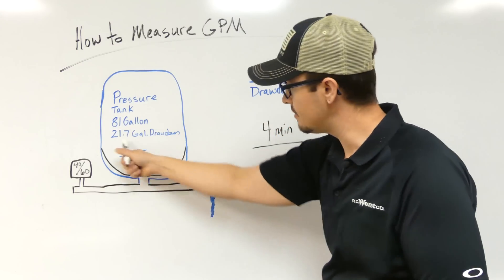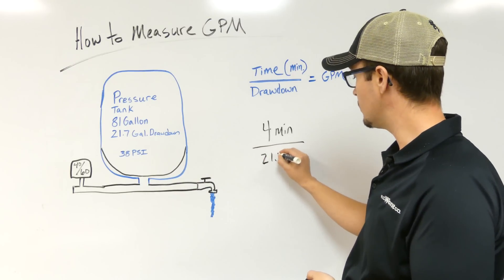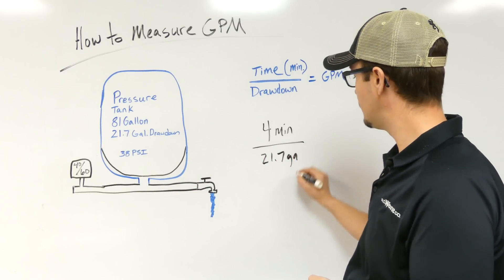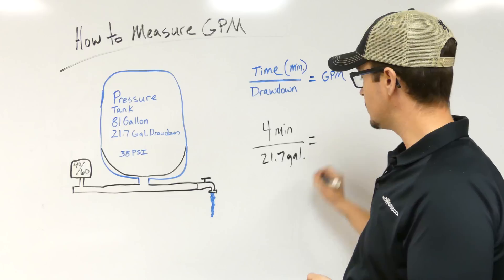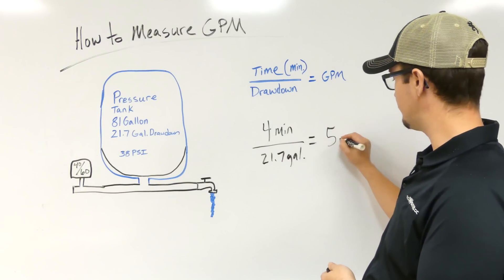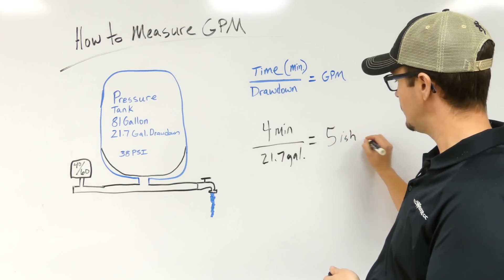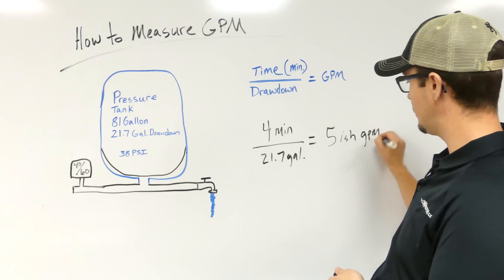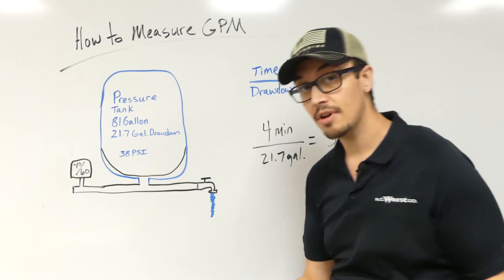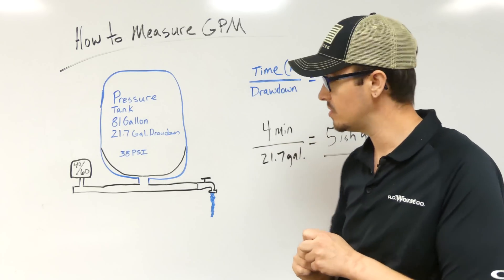Let's just do a quick one here. Let's say it took four minutes to do our drawdown of 21.7 gallons. So that gives us roughly five-ish gallons per minute. You can see just how quick and simple this method is.